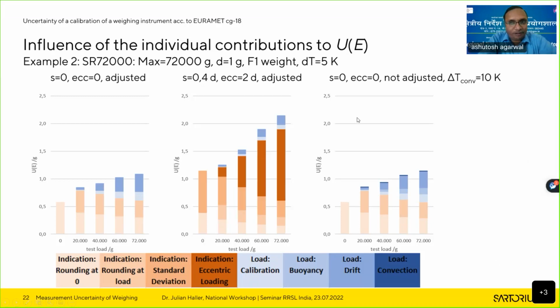How to address the drift induced by environmental conditions, particularly in case of highly sensitive balances like 5 digits and 6 digits balances? So I'm wondering what exactly is meant here by drift induced by environmental conditions. What is taken into account in the uncertainty calculations I've demonstrated is temperature changes. So that is taken into account as long as you do not have, let's say, too strong temperature fluctuations. If you just have a temperature change in your weighing room of, let's say, 5 Kelvin or 10 Kelvin, that is appropriately taken into account in the respective calculations. All other environmental conditions, if they drift slowly, should not have a significant effect on the result.